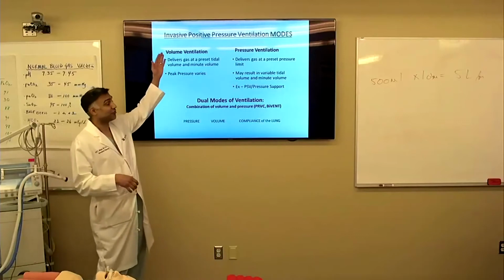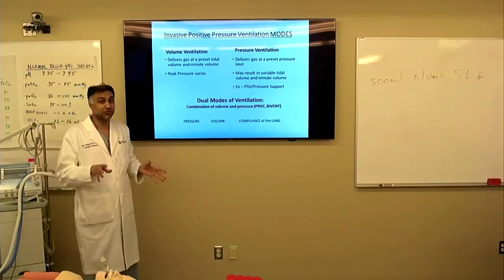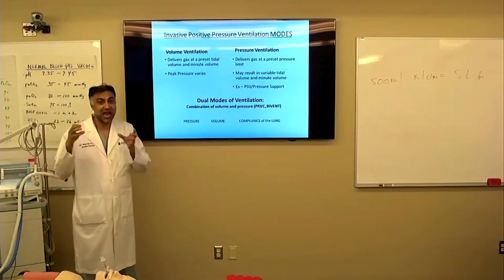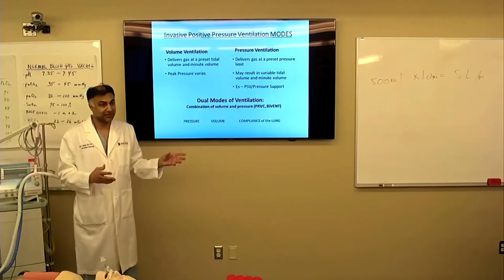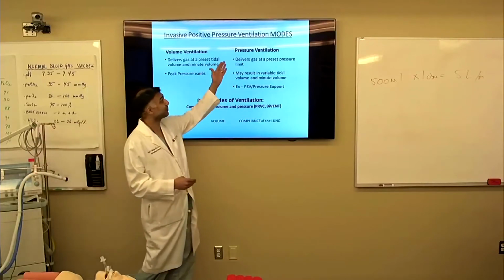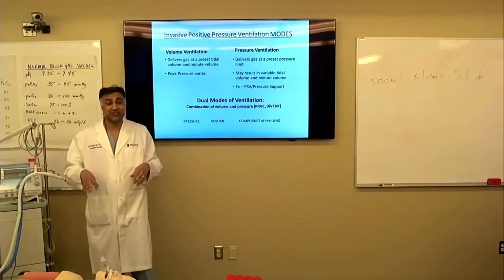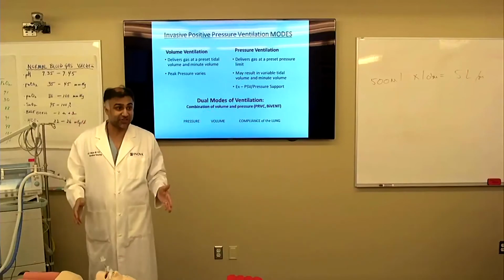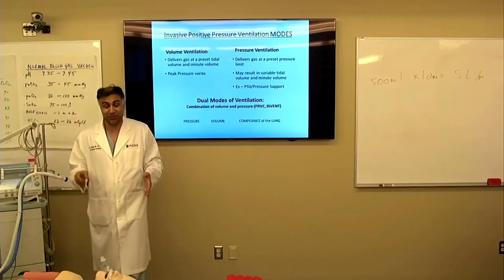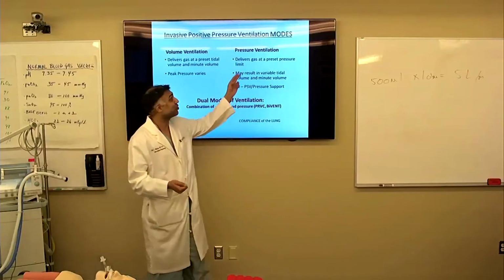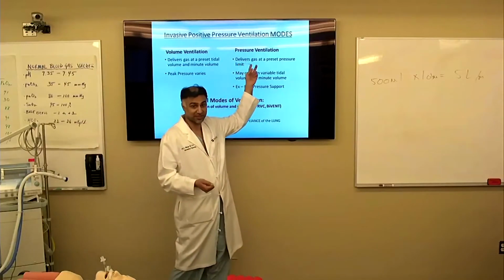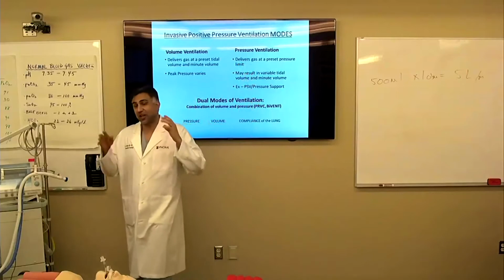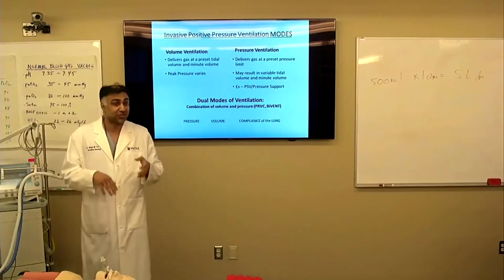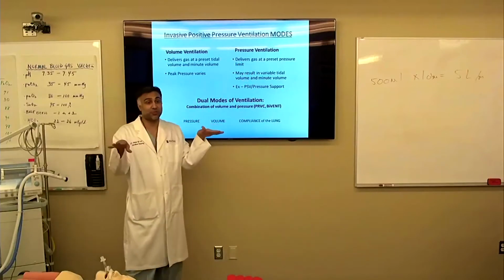Again, remember, with volume control ventilation, you control the volume, so we can determine how much air goes in with each breath. When we talk about pressure control ventilation, this means we can control the amount of pressure going into the patient, meaning that we set the pressure, but we don't set the flow or the amount of volume that goes in. So we say, well, we don't want to injure this person's lung, so let's make sure the plateau doesn't go above 30.